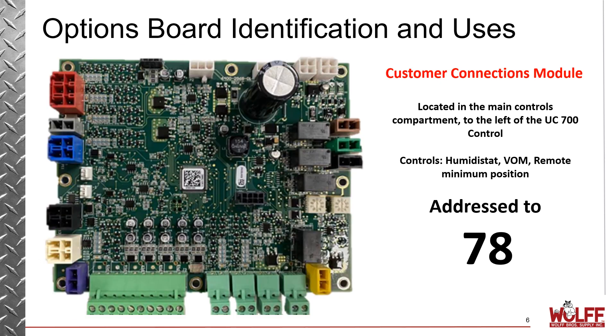Here we have the customer connections module. This module is located in the main controls compartment, just to the left of the UC 700 control. It's going to control options like the humidistat, the ventilation override, and the remote minimum position. This module must be addressed to 78.